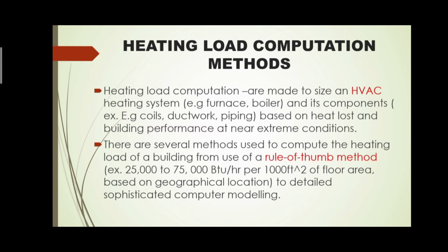Heating load computation methods. Heating load computations are made to size an HVAC heating system, for example a furnace or boiler, and its components, which are coils, ductwork, and piping, based on heat loss and building performance at near extreme conditions. So what is HVAC? HVAC is heating, ventilation, and air conditioning system.